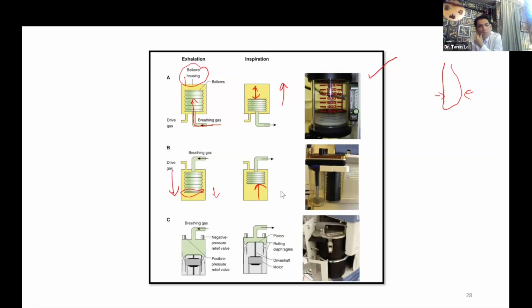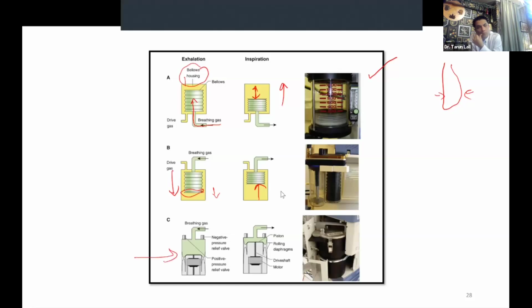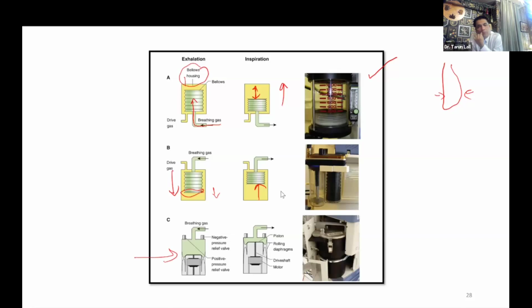In the older machines, especially older Drager machines, we have used descending bellows ventilators. But these days, mostly you will find ascending bellows, or in the newer Drager machines, you will also find a third type, the piston-driven ventilator, where you don't require any driving gas at all. It is a totally mechanical piston-driven device, connected to your computer, which decides the tidal volume, rate and other parameters as per your settings. So these are the three basic ventilator designs.